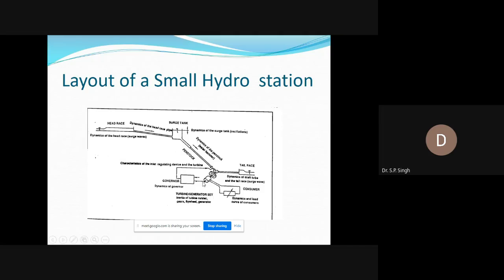Here again you can have a governor or load control. The purpose of the governor or load control is just to control the voltage and frequency. Either the governor or a dynamic load, or sorry, the consumer load, keeps on varying. So as the consumer load varies, we have to adjust the speed of the turbine to get a constant frequency.